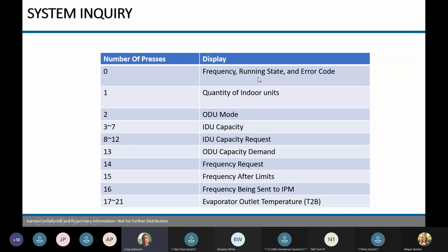So when you first open it and it's working, it's going to tell you the frequency of the compressor. So it's going to give you an idea of what range the compressor's in, if it's in half mode or full mode, running state, and that display is going to give you error codes as well.